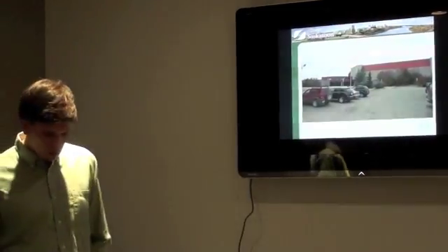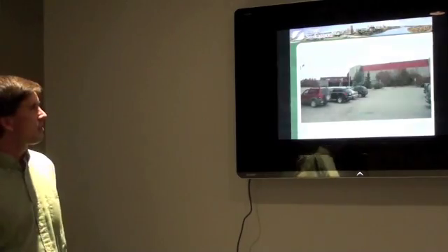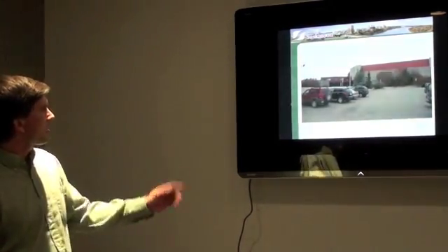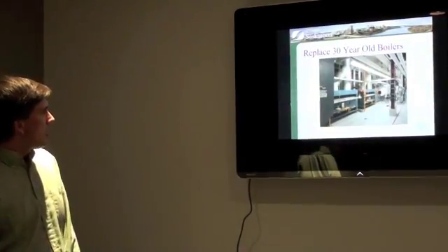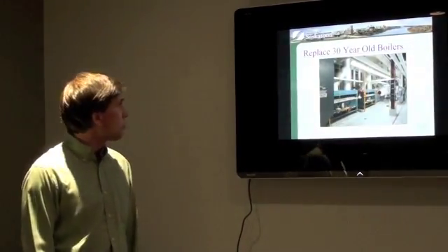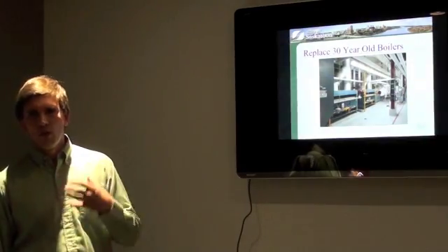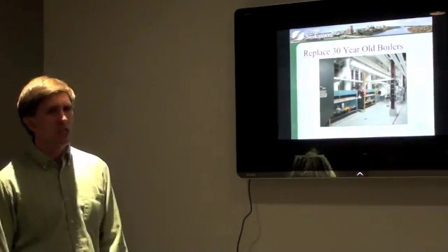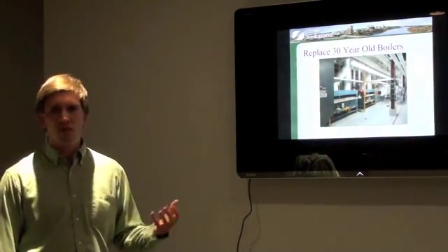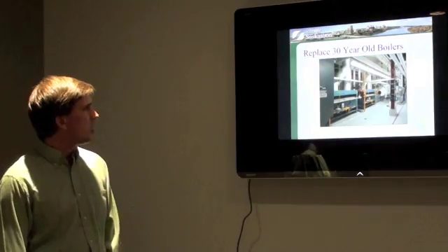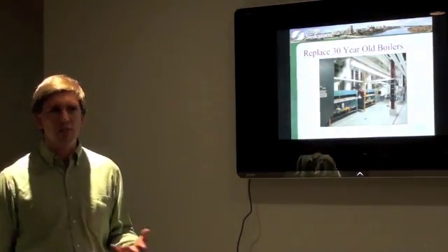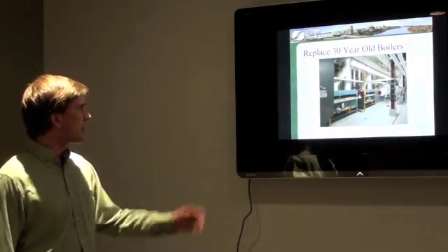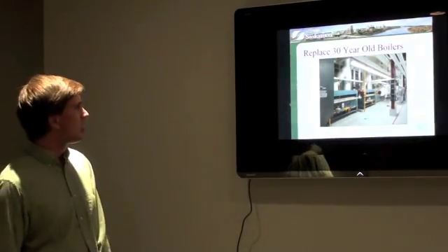Next is a project that we've got with the facilities department within the city, the main project at the Saskatoon Fieldhouse. At the Fieldhouse, they've got very old boilers, 30 years old. The older a boiler gets, the more inefficiently it runs, so there's extra energy loss, an extra demand on ongoing maintenance costs, and the reliability drops. So it becomes a liability for maintaining the temperature you're providing to the users of the facility. So, at the end of their service life, it was time to replace them.